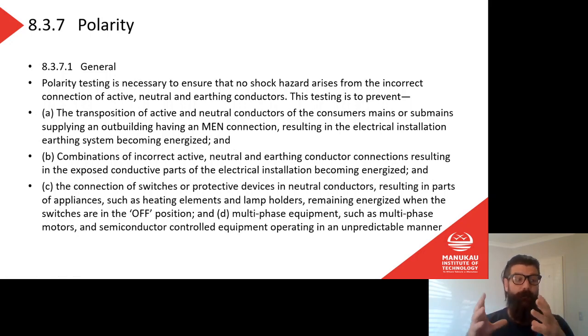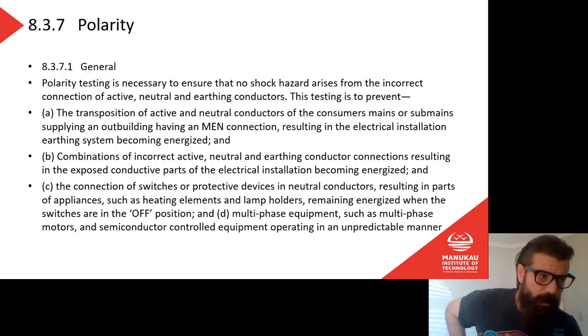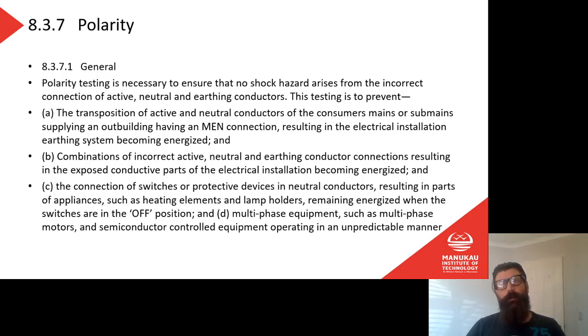Right, so our earthing system is going to be connected to all the metal parts of an installation. So if you've got a metal bench, that'll be connected to the earthing system. The idea is that if somehow that metal bench got live, the earthing system will provide a path back to neutral and therefore trip the circuit breaker. So by the time I come along and touch the bench, the circuit breaker has blown and there's no voltage there. If your main supply coming into the building accidentally gets transposed, phase and neutral, and all my earths in the system are connected to the neutral, then I actually might liven that kitchen bench accidentally.